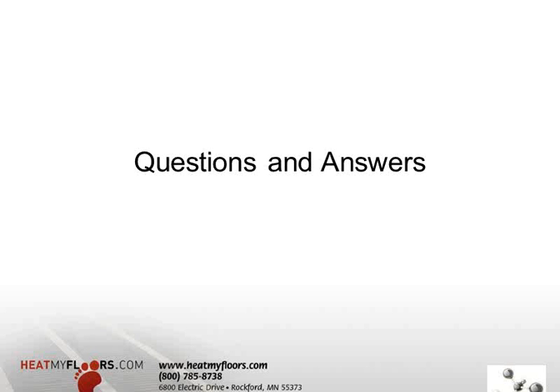Second question here is, any recommendations for area rugs on a wood floor with STEP Warmfloor installed under a 3/4 inch thick solid wood floor? No, you can certainly put area rugs over the top of your hardwood floors. It's not going to have any effect with the STEP Warmfloor. In fact, the STEP Warmfloor is going to work less in that square inch area of the area rug, because it's going to come up to temperature very quickly, since you're trapping the heat. Once it comes up to temperature at 82 degrees, it's going to self-regulate underneath that wood floor. So you're going to use less energy there as opposed to an area where the area rug isn't, where the heat is going to transfer through that wood subfloor, through that 3/4 inch solid wood floor and into the home. So area rugs, no problems on top of the wood floors with STEP Warmfloor.